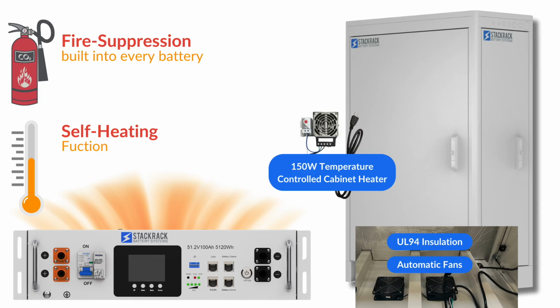Each battery module features a self-heating function, which will warm the battery cells in very cold climates. We also feature integrated aerosol fire suppression devices into every battery module for additional safety. Inside our battery cabinets, there's a UL94 insulation lining for additional thermal protection and fire safety. For temperature control, we feature automatic cooling fans in every cabinet. We also feature the ability to add 150-watt cabinet heaters to our 4 battery, 6 battery, and 10 battery cabinets.